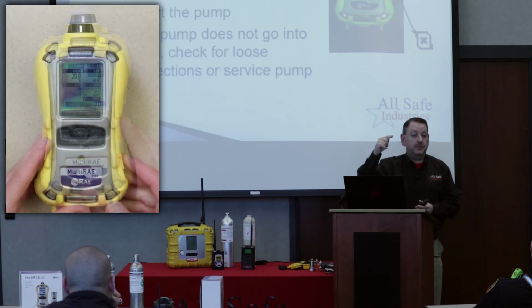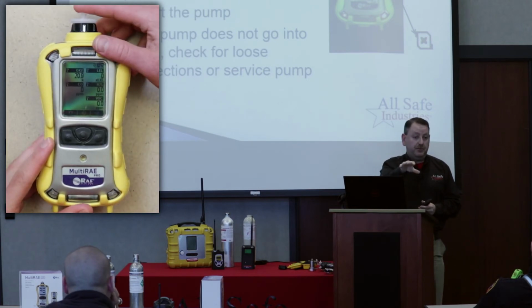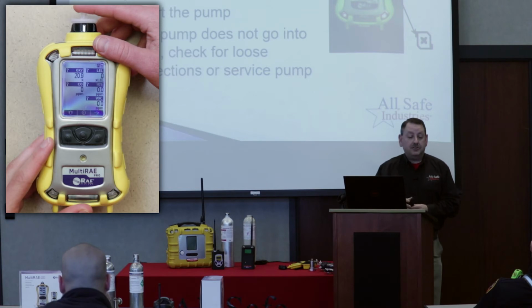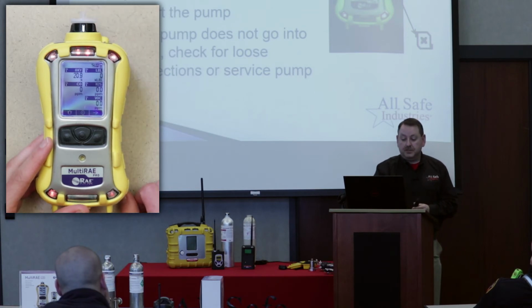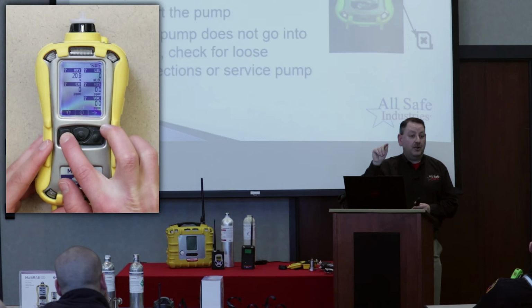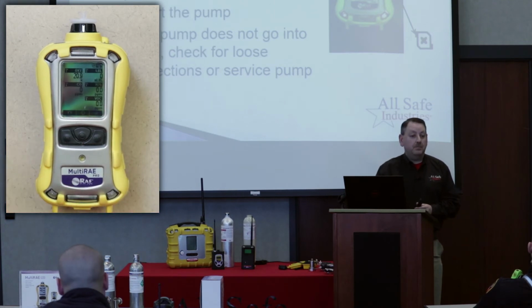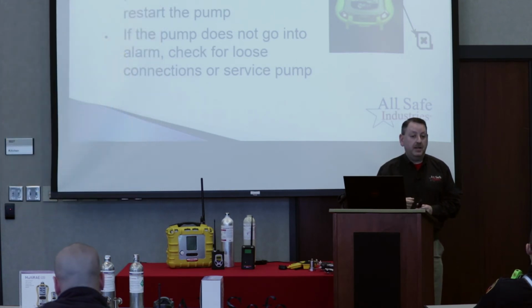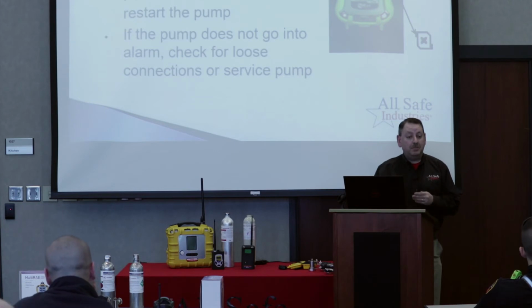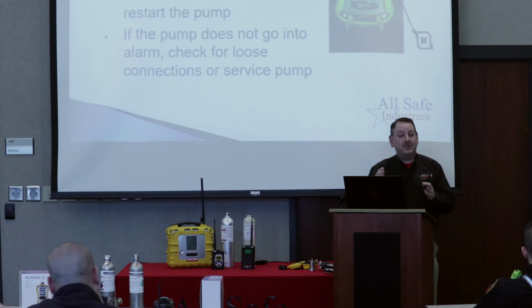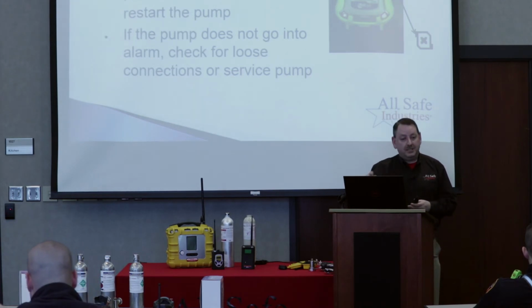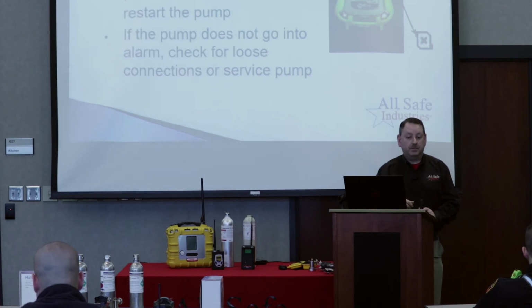You're just going to put your finger over the inlet of the instrument after this fresh air cal's done, and it's just going to stall out the pump. So you'll see that the little pump icon has an X on it now, and then to restart the pump, you just press the Y button, okay? Now the tricky thing is you do have to be on page 1 when you press the Y button to restart the pump. If the beeping and the flashing kind of freaked you out and you've hit another button and moved on to another page, it's going to stay in that stall mode until you're back to page 1. So on page 1 is where you'll hit the yes button to restart your pump.